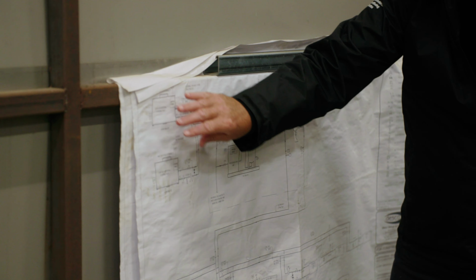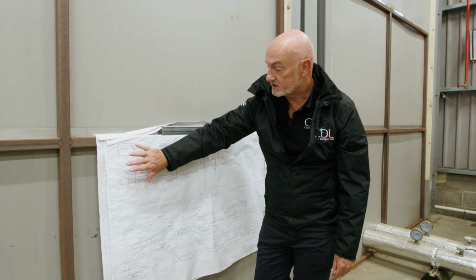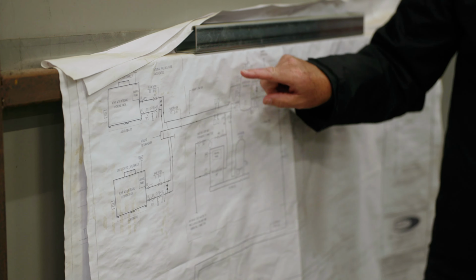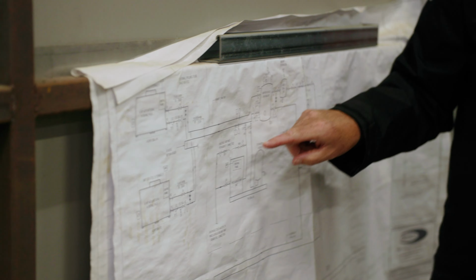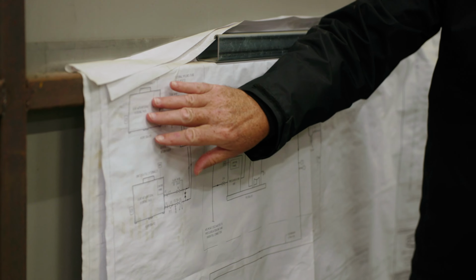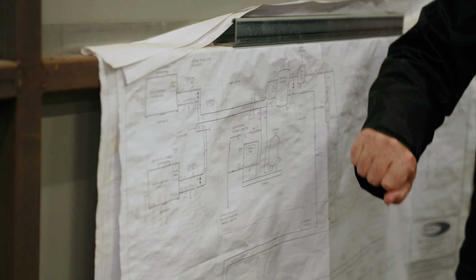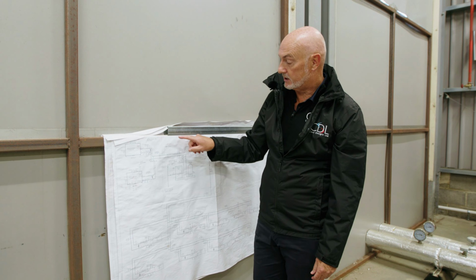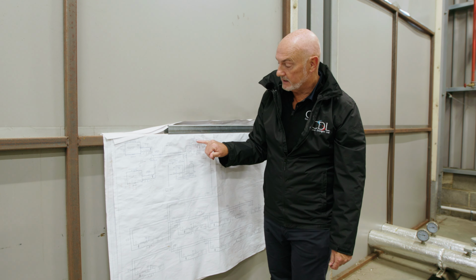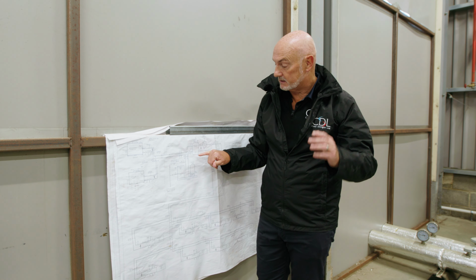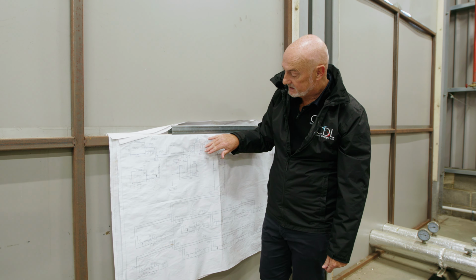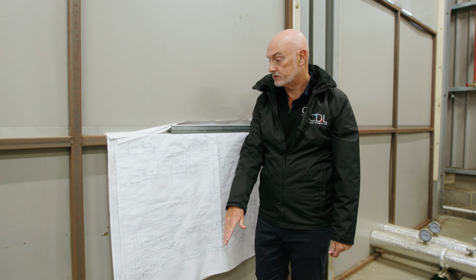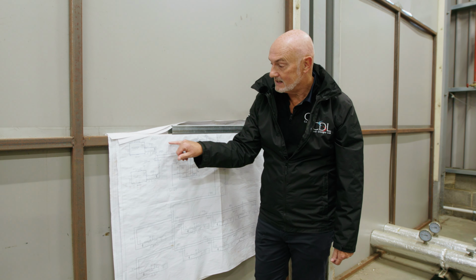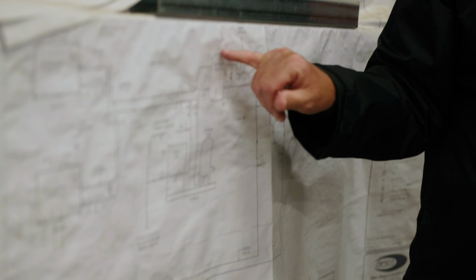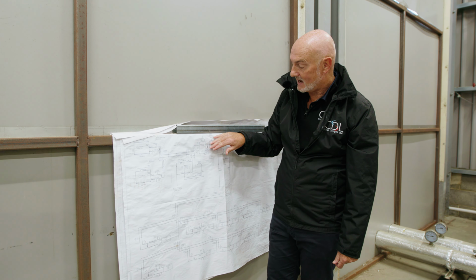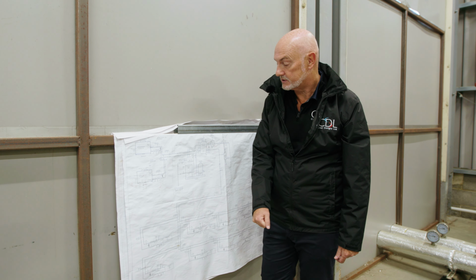The two air source heat pumps we've just been talking about are outside. This is what's called the primary circuit. So this is a circulating circuit of water that goes backwards and forwards from the pumps inside the air source heat pumps. And this is a 38 degrees C circuit, and then into the buffer vessel, which is the big tank beside us. And from there we take the secondary circuit, which goes off with the hot water. So this heat generating section is called the primary circuit, and this area is called the secondary circuit.